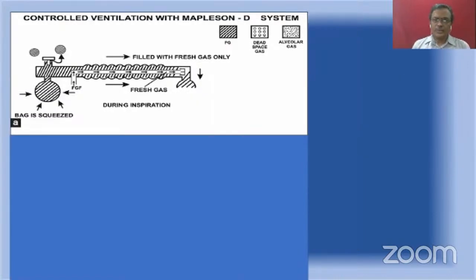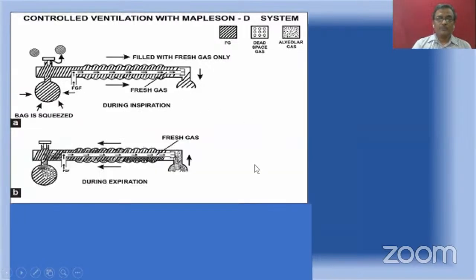Now let us see what is going to happen during controlled ventilation. In the first picture, the whole system is filled with fresh gas. The anesthetist is squeezing the bag, and look at the valve. Some of the fresh gas is lost into the atmosphere, and the other part of the fresh gas is going towards the patient during inspiration. Now, the expiration has reached.